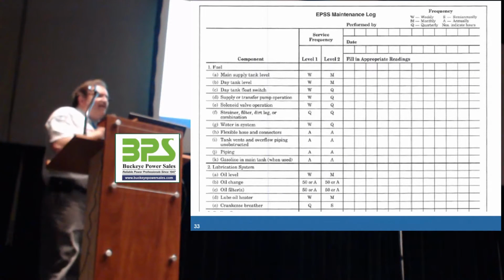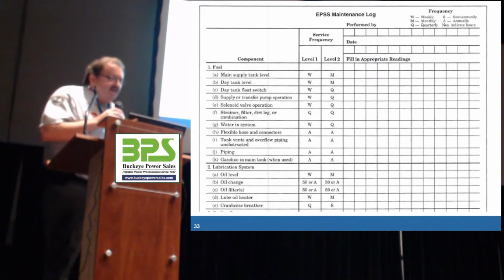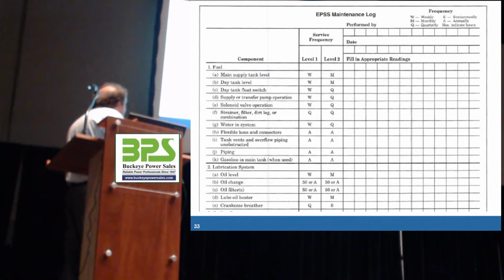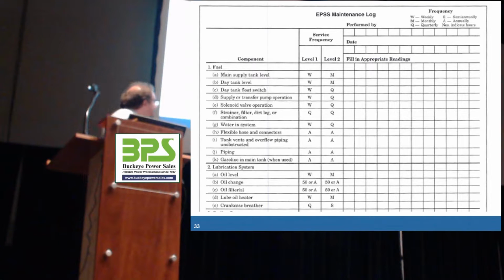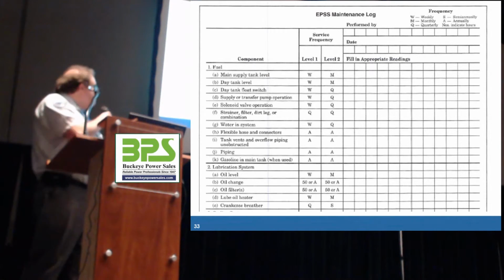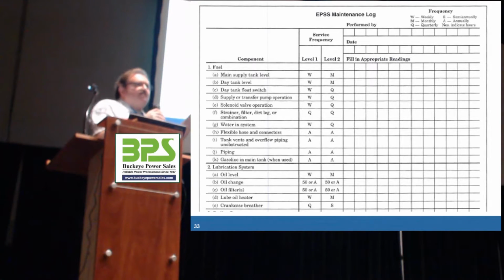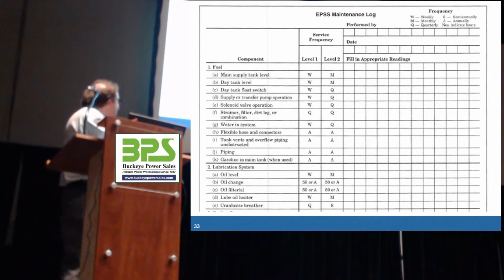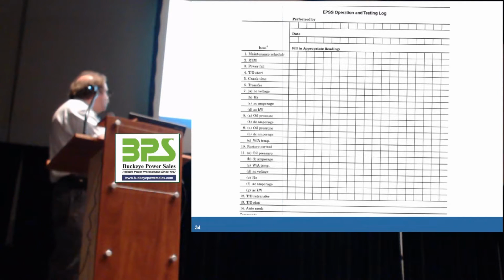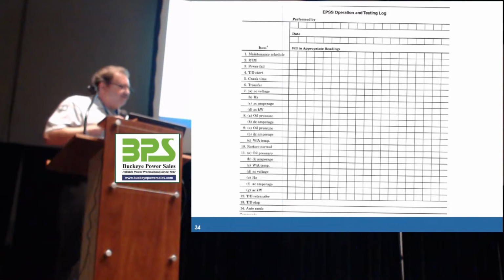The other is the maintenance log, and this goes hand in hand with the checklist. Again, this maintenance log is basically the same, except you have a space for date and some sort of identification of who did the service, whether you should weekly check the day tank, whether you should quarterly check the transfer pump, annually check the tank vents, annually inspect the piping, check the oil level weekly, change the oil once a year, check the lube oil heater, check the crankcase. So this is where you document that you check that. And then it goes on to have a place for you to document the voltage and the oil pressure and the coolant temperature. When you're doing that monthly transfer test, you can document how long it took the system to transfer over. So this is what that looks like.